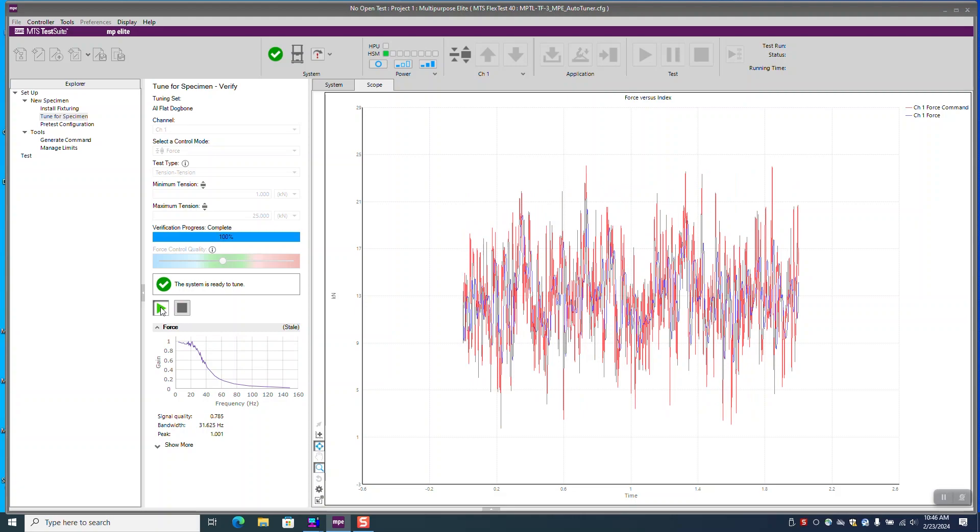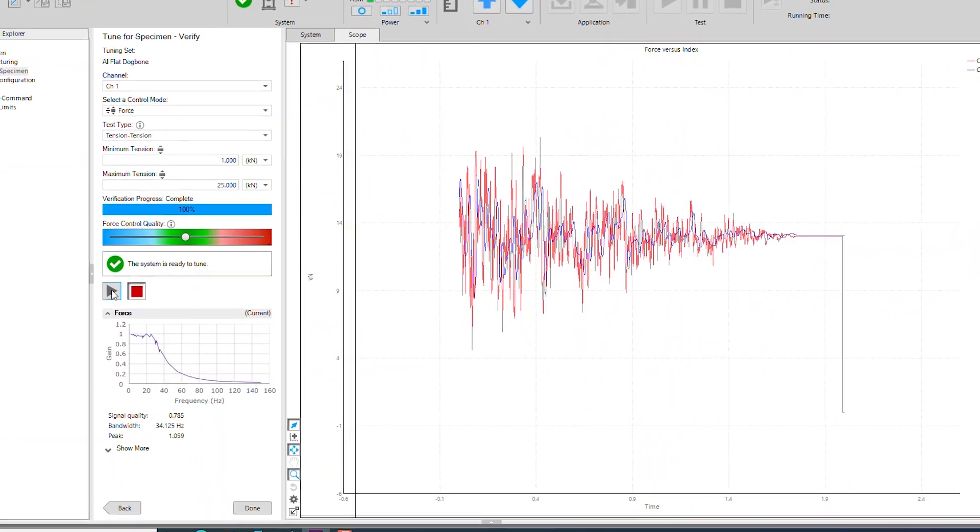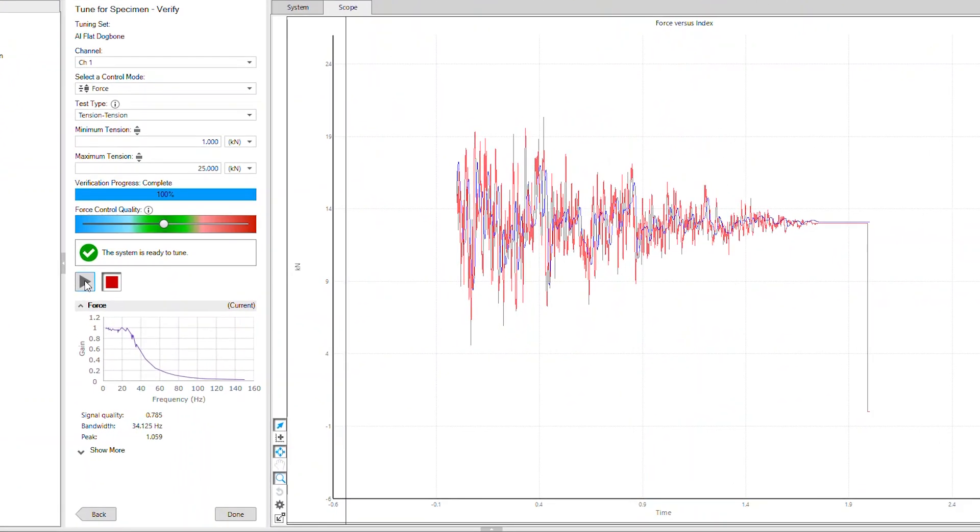Once the auto-tuning is complete, the software provides the specimen characteristics that the system then uses to set the proper PID tuning values. These values will vary depending on whether your loading method is axial or torsional.